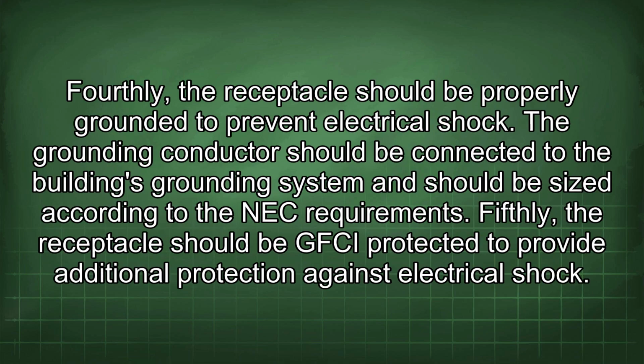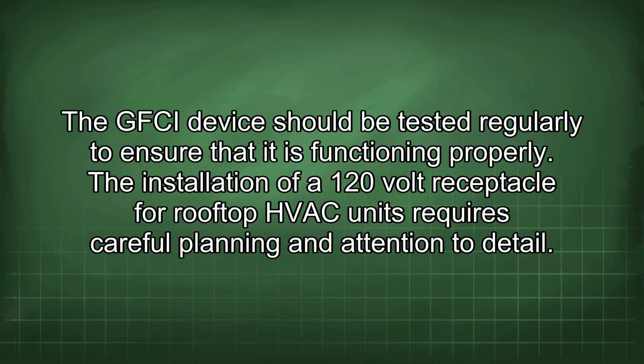Fourthly, the receptacle should be properly grounded to prevent electrical shock. The grounding conductor should be connected to the building's grounding system and should be sized according to the NEC requirements. Fifthly, the receptacle should be GFCI protected to provide additional protection against electrical shock. The GFCI device should be tested regularly to ensure that it is functioning properly.